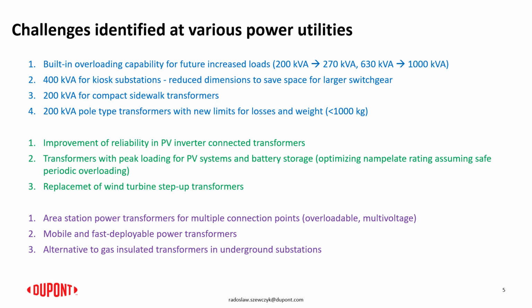Of course, with the wind turbine transformers, there is a growing size of those, including the large transformers up to 15 MVA and 66 kilovolt class for the offshore applications. But there is a big demand for the replacement of the transformers in repowered systems where the older turbines are upgraded, and this might require the new turbines to be installed, or at least the critical components of the turbines are replaced with the new ones. So sometimes the new transformers of larger power capacity are installed in the same confined space which was provided for the older, smaller transformer.